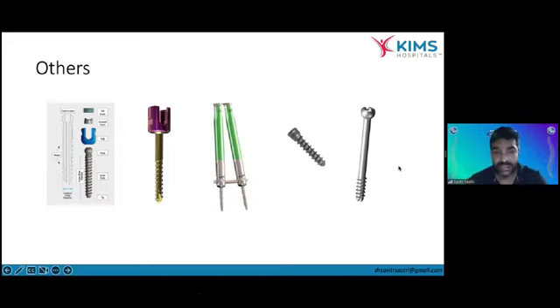The second screw that we see here is a screw that is used specifically in the craniovertebral junction. And this has a smooth surface followed by the threads. And this is used in C1 screws to make sure that the threads don't irritate the C2 ganglion. The third screw that we see here is the minimally invasive screw, where the screws are attached to either a tower that is welded to the screw that can be broken off, or they have towers which can be snapped onto the screw and then unscrewed.